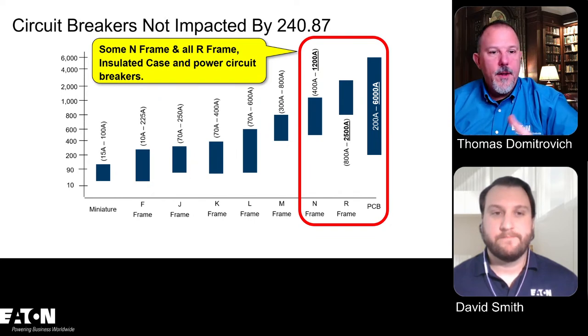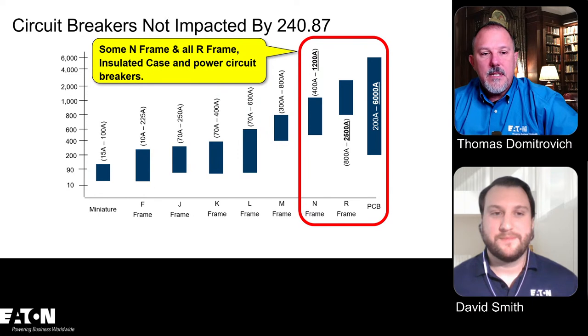All right, here we go. What is the typical reduction in incident energy when the requirement goes to 800 amp breakers? What is the typical reduction as far as amount of incident energy? It could be quite significant. We can run some numbers, and I'll do that a little bit later.